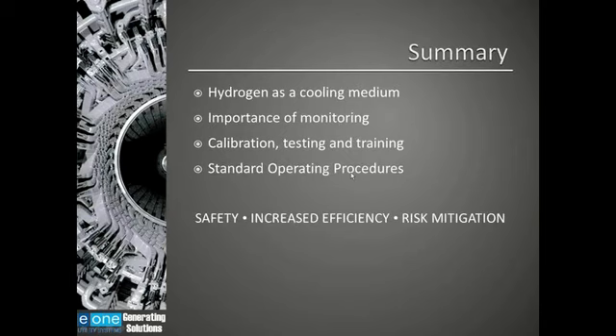In closing, we know that hydrogen is a very effective cooling gas. By using hydrogen as a cooling medium, we can get more megawatts without increasing the size of the generator. Again, as I mentioned earlier, more megawatts per pound of iron by using hydrogen as a cooling gas. We discussed the hydrogen auxiliary system and the importance of monitoring certain critical parameters. We discussed the need for well-written test procedures, training programs, calibration schedules, and standard operating procedures, and the need for proper tools and test and calibration equipment.